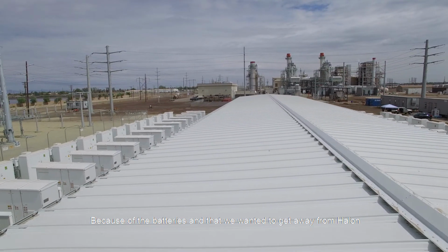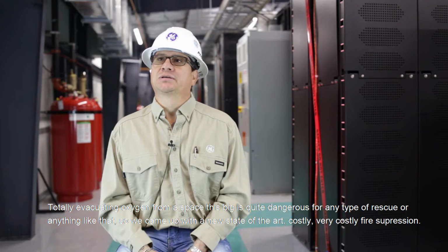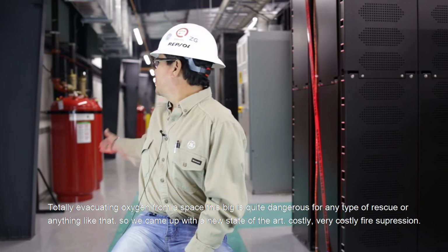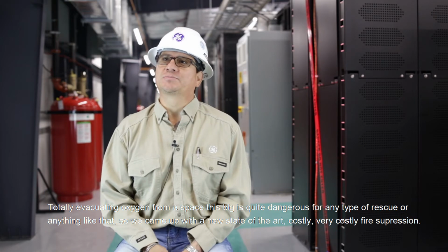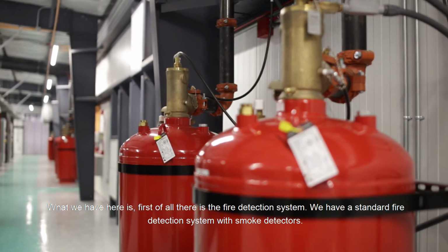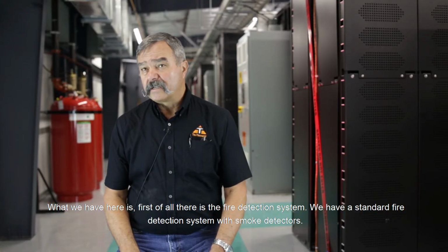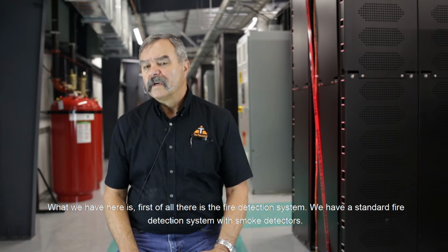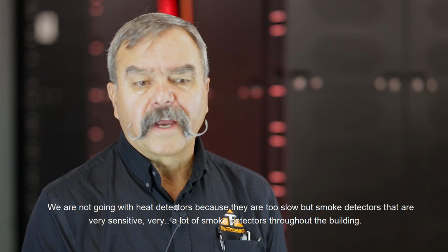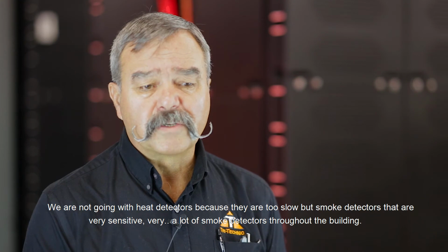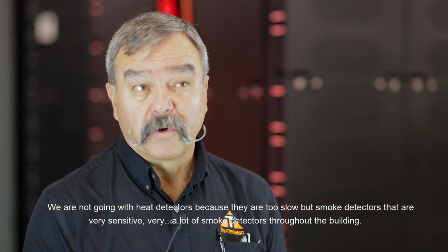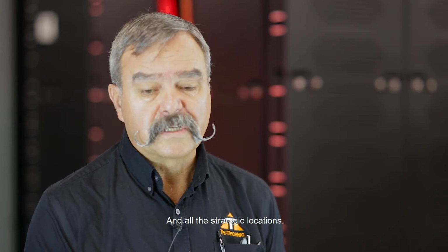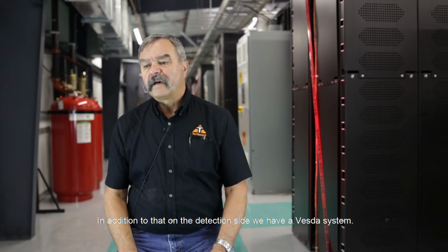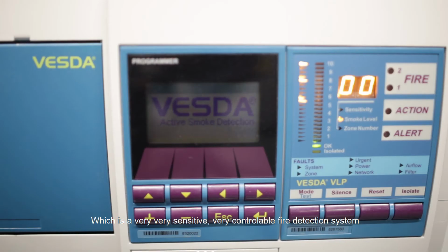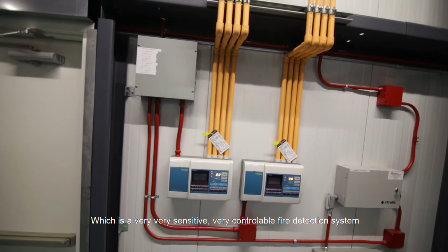Because of the batteries, they wanted to get away from halon and totally evacuating oxygen from a space this big. It's quite dangerous for any kind of rescue or anything like that. So we came up with a new state-of-the-art, very costly fire suppression. First of all, there's the fire detection system. We have a standard fire detection system with smoke detectors, and we are not going with heat detectors because they're too slow. But smoke detectors, very sensitive, a lot of smoke detectors throughout the building in all the strategic locations. In addition to that, on the detection side, we have a VESDA system, which is a very, very sensitive, very controllable fire detection system.